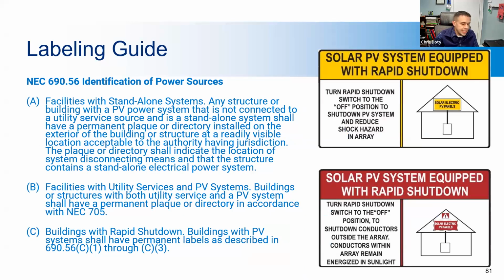The 2017 NEC expanded on labeling requirements with even more details. So this label alerts first responders and others that the system is equipped with rapid shutdown. The red is for string inverters, yellow is for DC optimizers and microinverters.